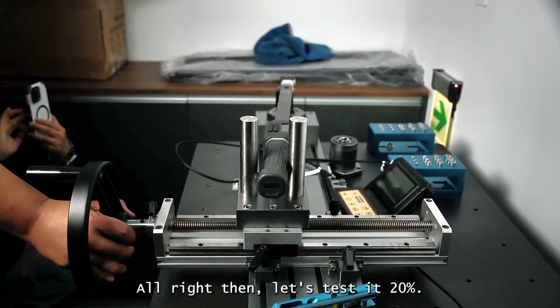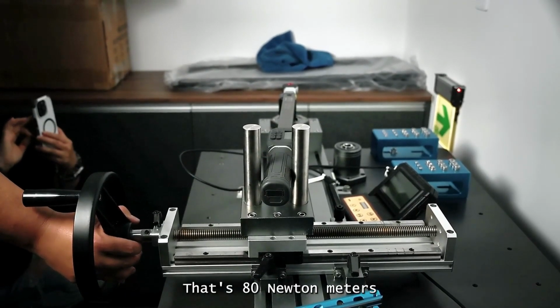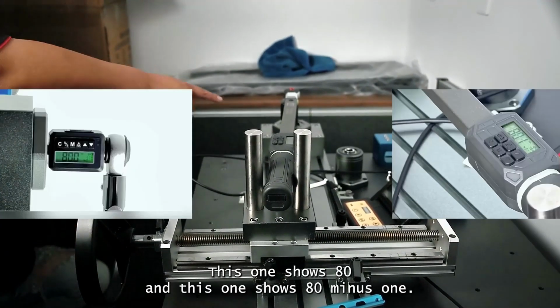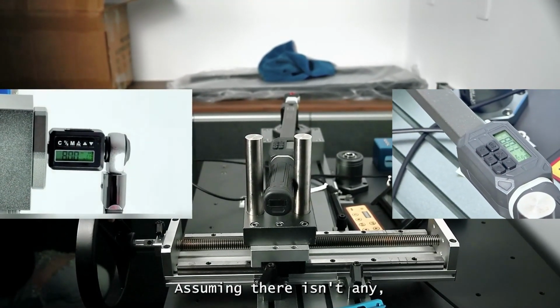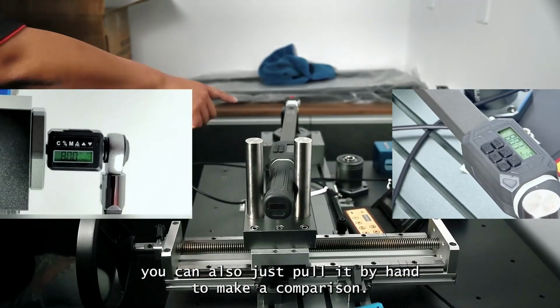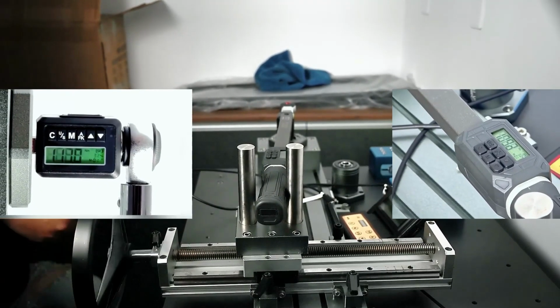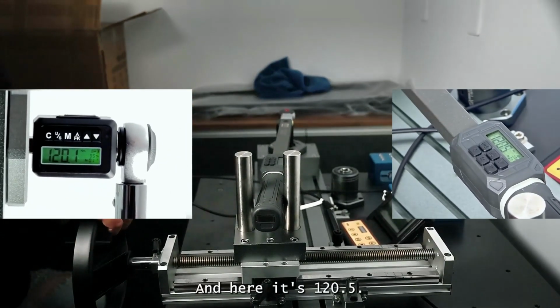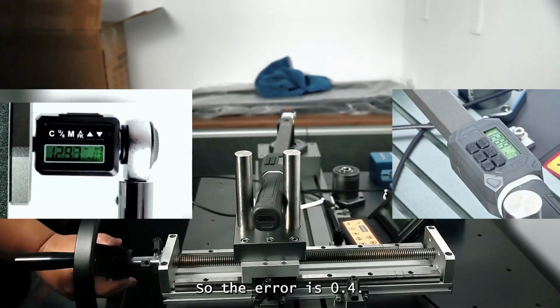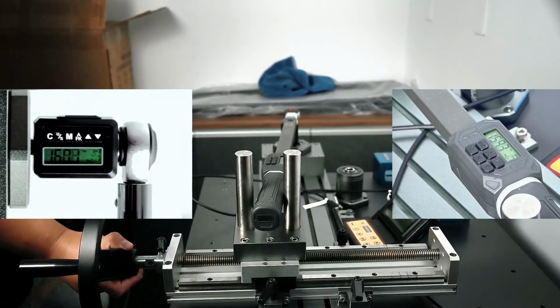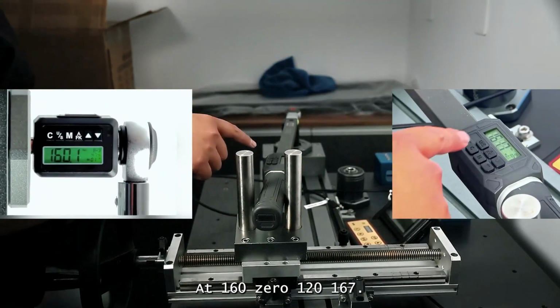Alright, then let's test at 20%. At 40%, that's 80 Newton meters. Okay, this one shows 80, and this one shows 80 minus 1. Even without car manufacturing equipment, you can also just pull it by hand to make a comparison. Now let's do 120 Newton-meters. Here it's 120.1, and here it's 120.5, so the error is 0.4. At 160, here it's 161.7. Okay, let's move to the next point.